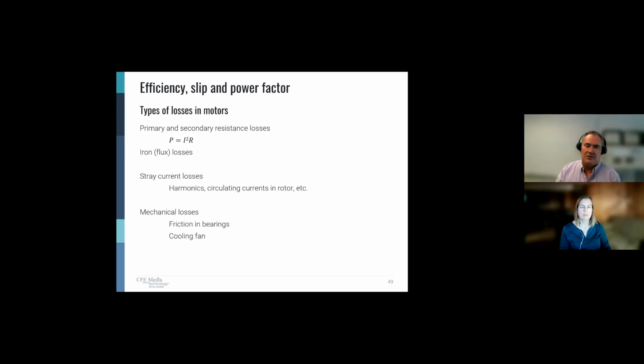There are types of losses in motors. There's primary and secondary resistance losses. You should remember the basics, power equals I squared R, okay? There's iron losses or flux losses as the magnetic field runs around the iron. There's stray current losses, harmonics, circulating currents in the rotor, etc. There are mechanical losses, frictions in the bearings. Do you have a fan? You know, the fan requires energy to turn and move that air. All of these things add up to costs or losses in our motor.